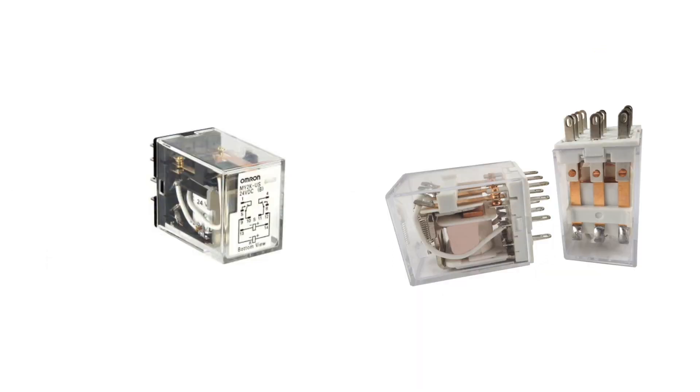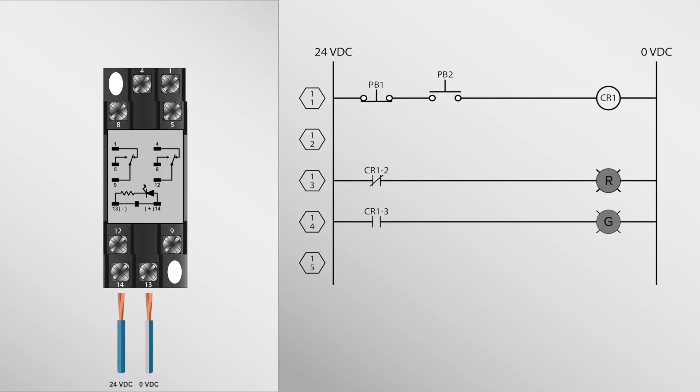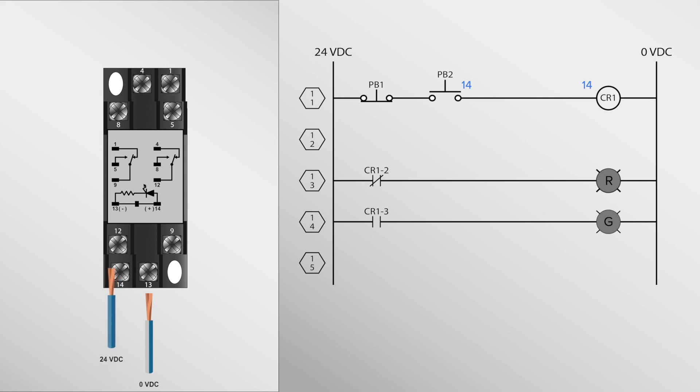Relays will typically have a wiring diagram on the side or in the front of the relay. We have here a drawing example of a relay. The 13 and 14 are where you will wire to power the relay. So with the circuit we have provided, the positive side being 14, you would take the wire from the push button and wire it to 14. Now you take a wire and wire it to the 13 and from the 13 to negative power.